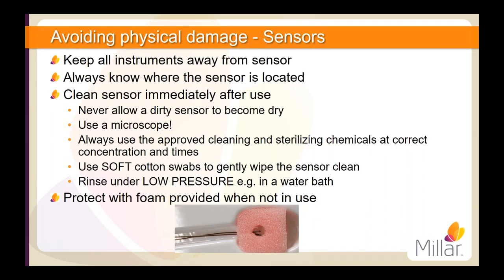Soak the sensor end of the catheter in Terg-A-Zyme or another approved cleaning agent for the specified period of time before cleaning. Always use a microscope when cleaning the catheters and use a soft cotton swab to gently wipe the sensor clean. Once clean, the sensor should be placed in the foam provided so that the sensor itself sits in the hole within the foam. This foam will help protect the sensor from electrostatic discharge as well as physical damage during handling or storage.